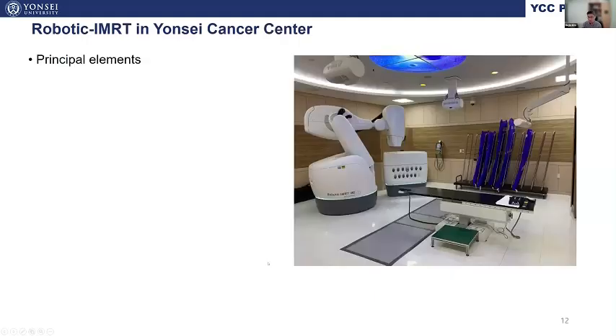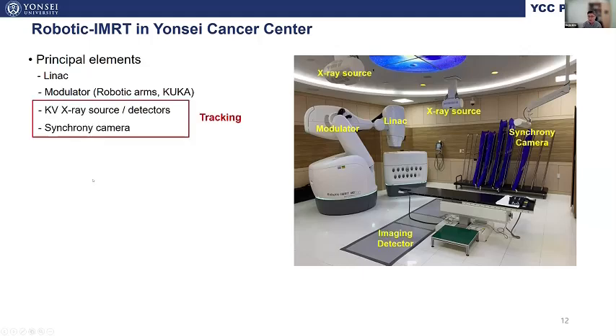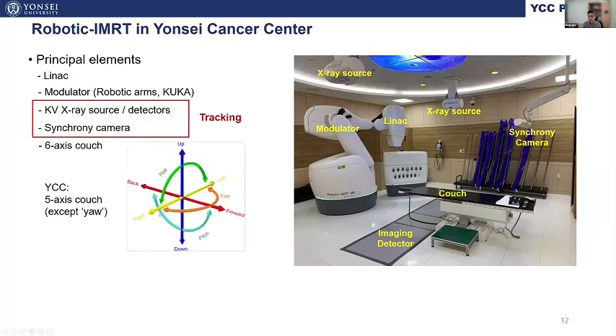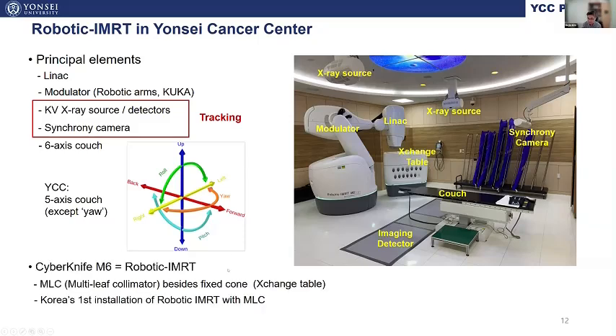To better understand the characteristics of robotic RT, the following image shows its principal components. The linear accelerator is placed at the end of the robotic arm, named KUKA, as I told you. A kilovoltage (kV) X-ray source, detector, and synchrony camera are required for motion tracking and image guidance. Also, CyberKnife can offer a 6-axis couch. However, we are currently using a 5-axis couch. Our cancer center is the first institution in Korea that installed the CyberKnife M6 robotic RT.